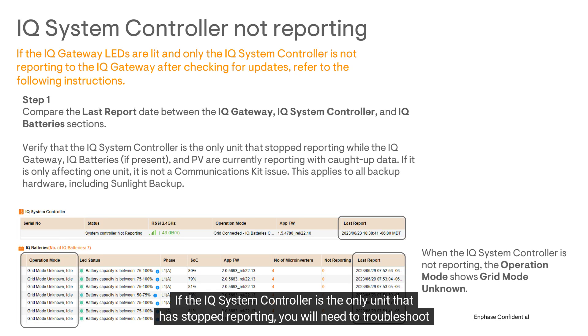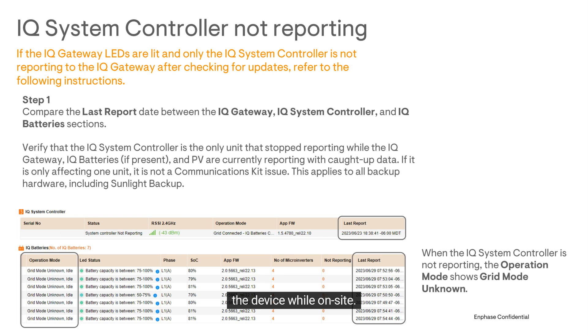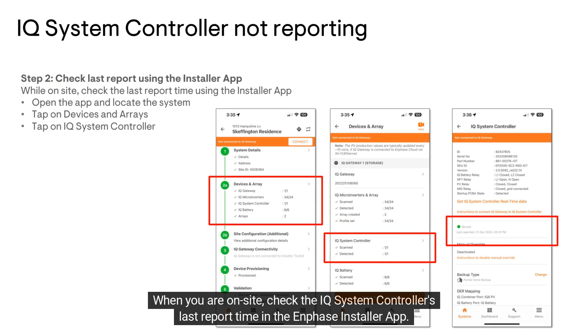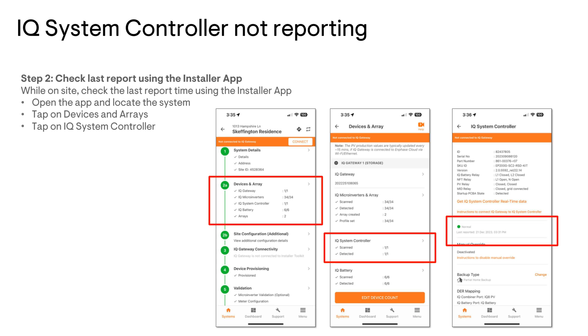If the IQ system controller is the only unit that has stopped reporting, you will need to troubleshoot the device while on-site. When you are on-site, check the IQ system controller's last report time in the Enphase installer app.